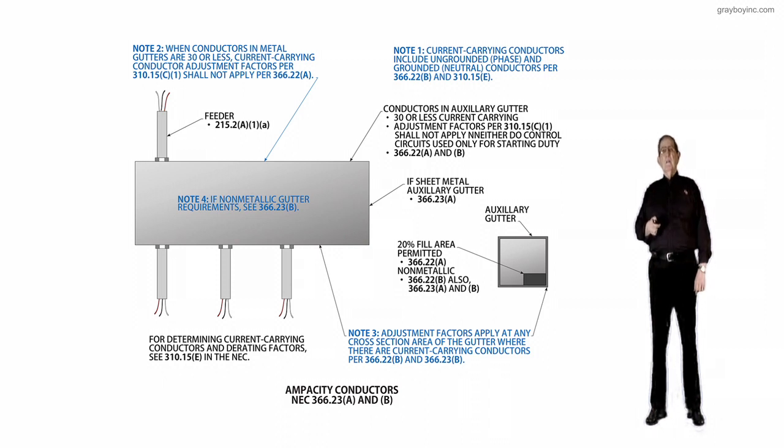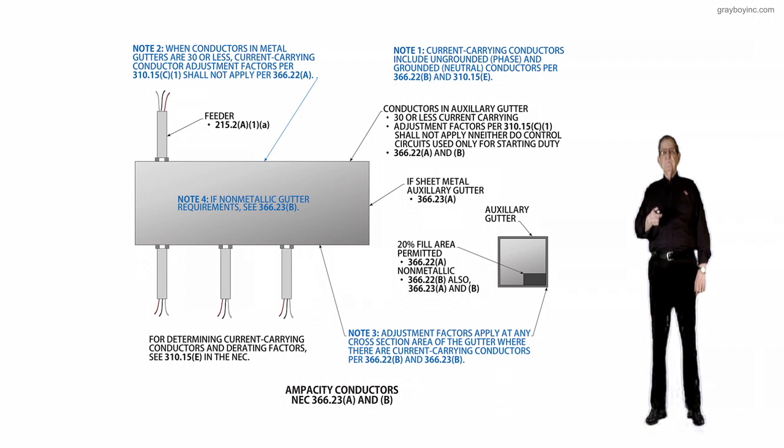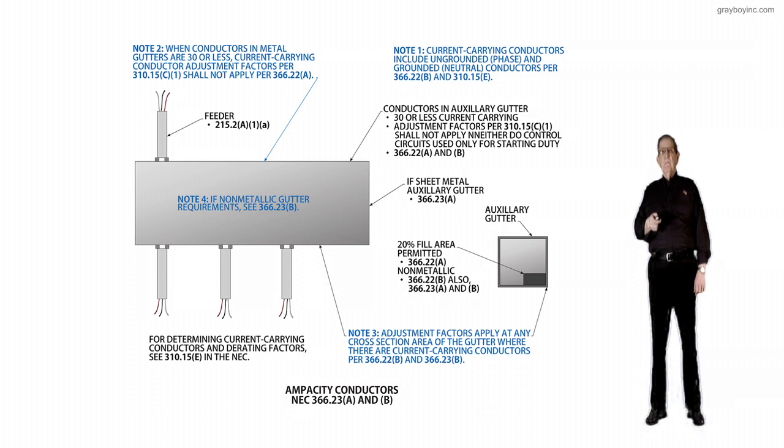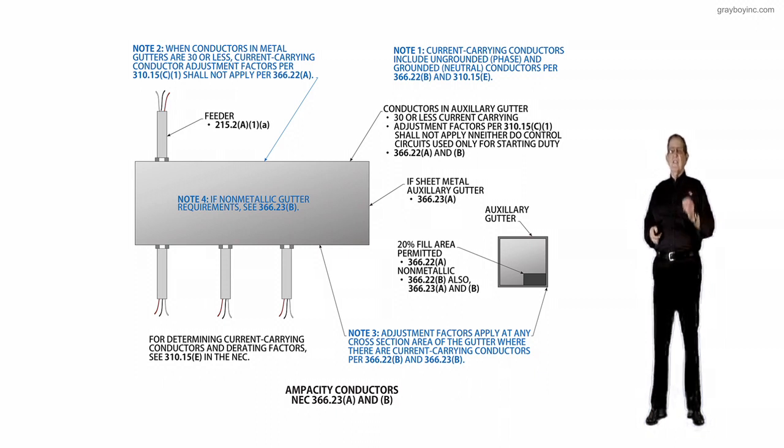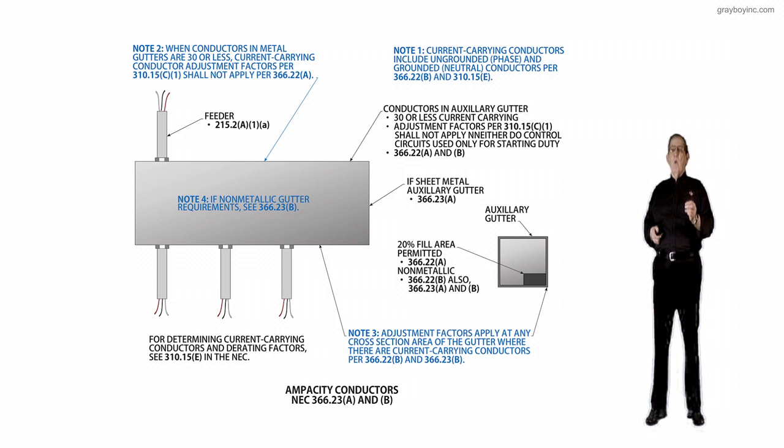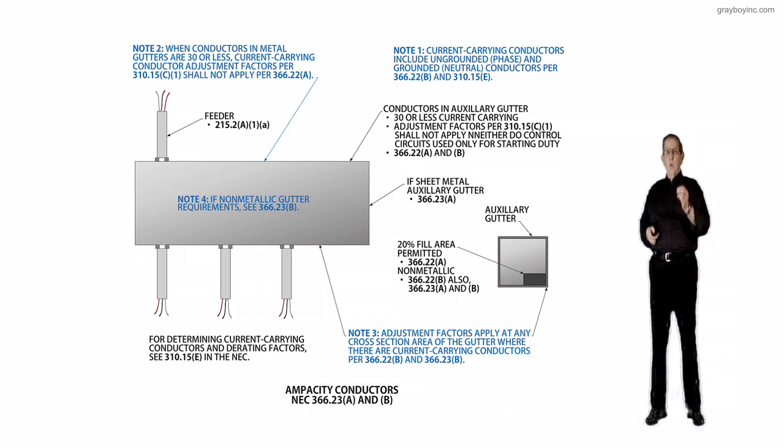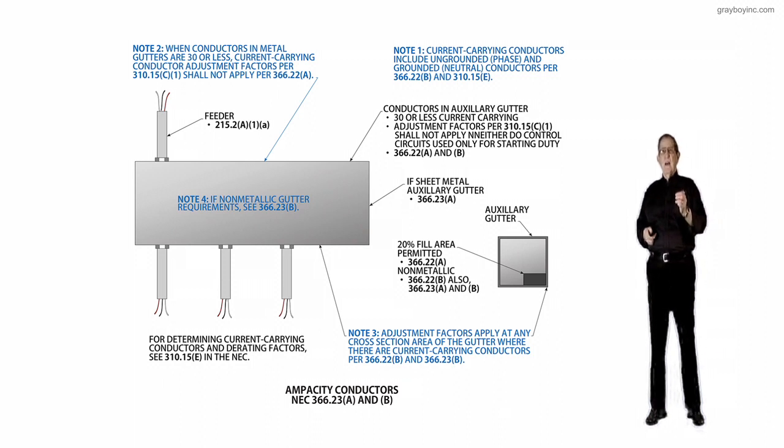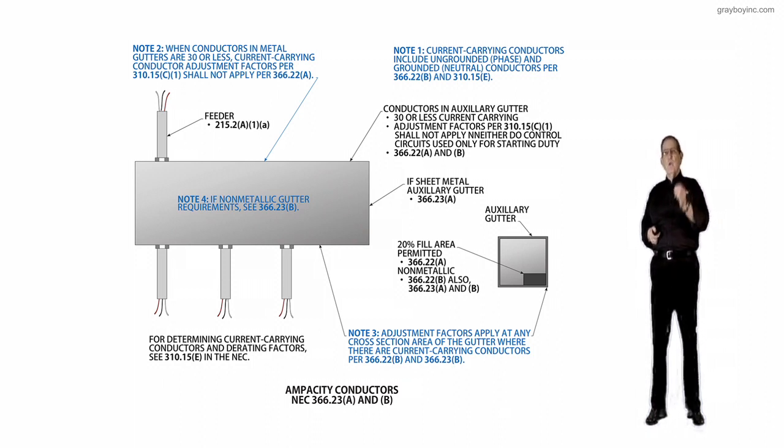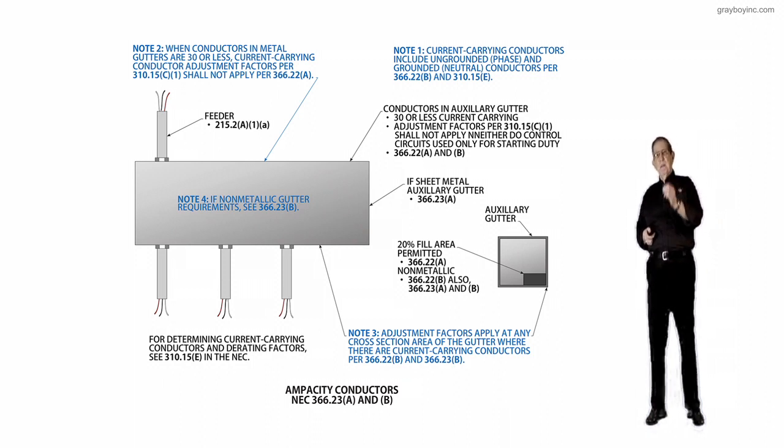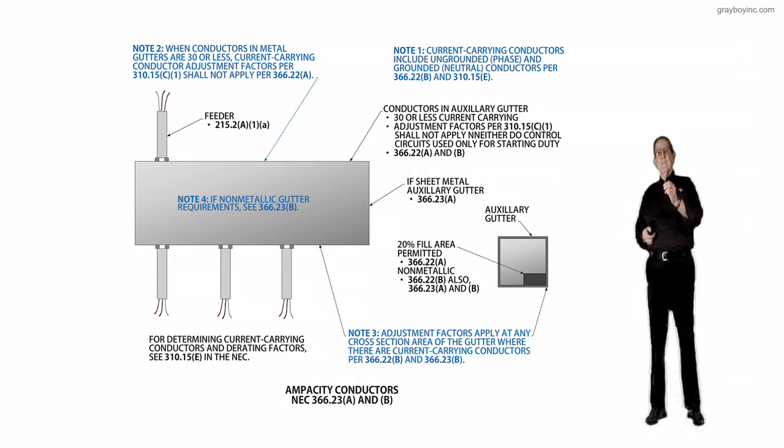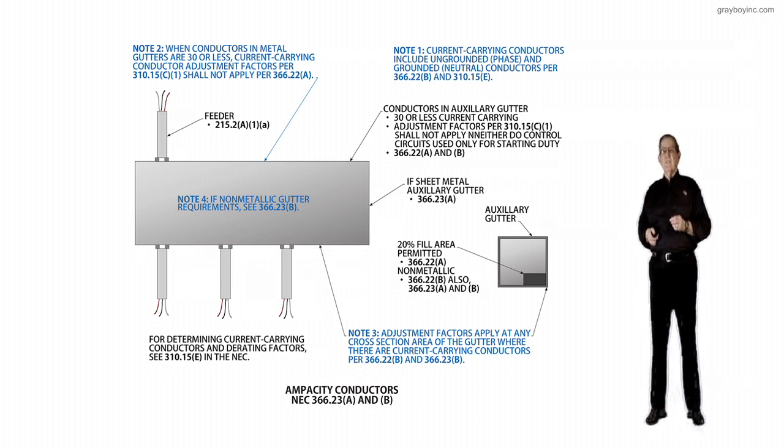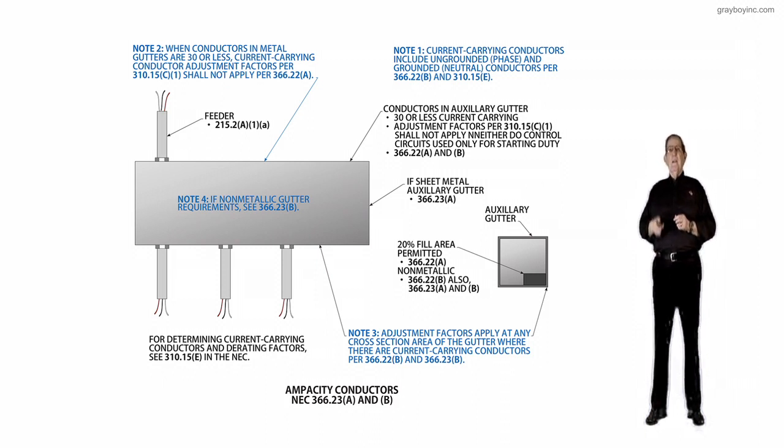Now notice, many times the inspector would look at this auxiliary gutter, and you see the conduit here to the right comes down to maybe a disconnect, and then measurement from that disconnect over. And if you're over 30 foot, they classify you as a wireway by 366.12B. So that's how you would classify a wireway.